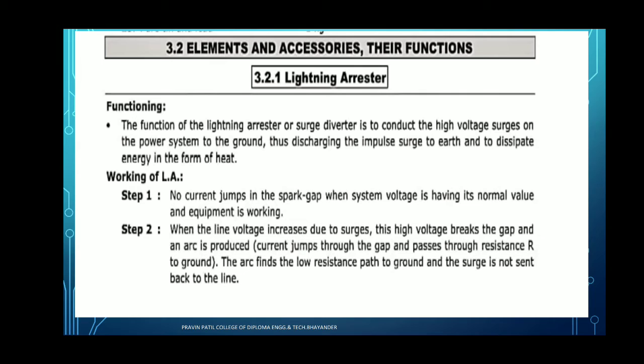Another function of the lightning arrestor: it is the device which diverts high voltage surges directly towards the earth. One terminal of the lightning arrestor is connected to the overhead line and the other terminal is connected to the earth. Now we have to see the working of the lightning arrestor.